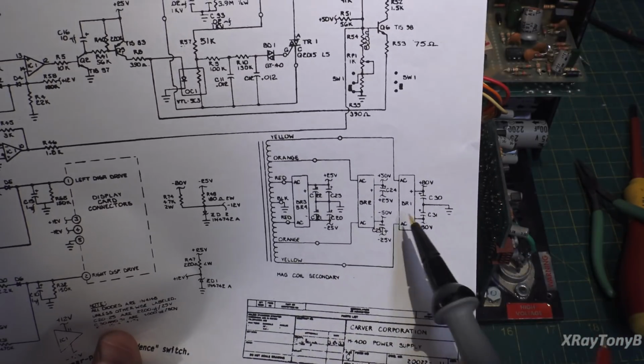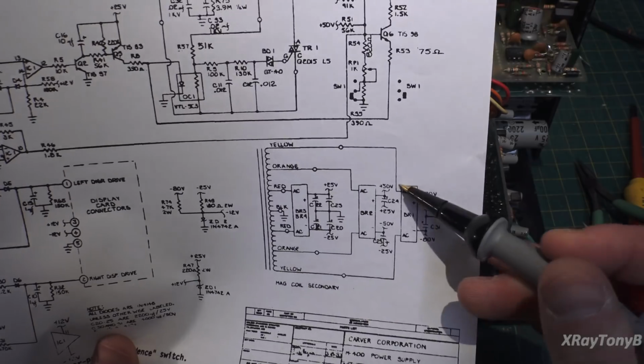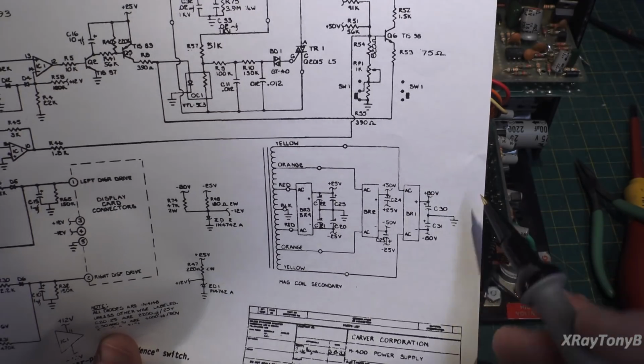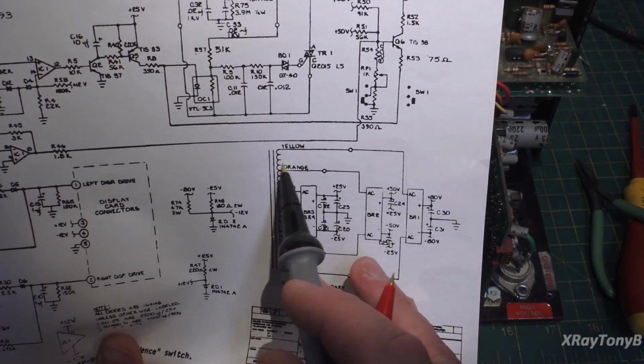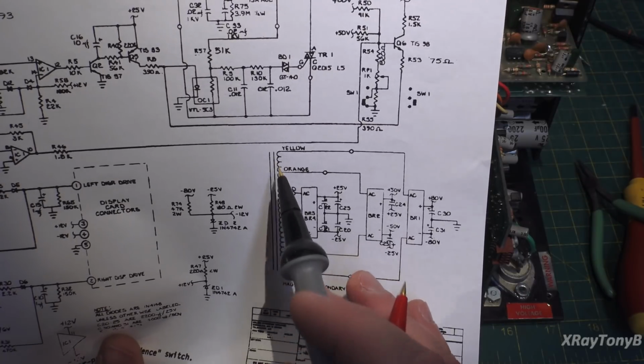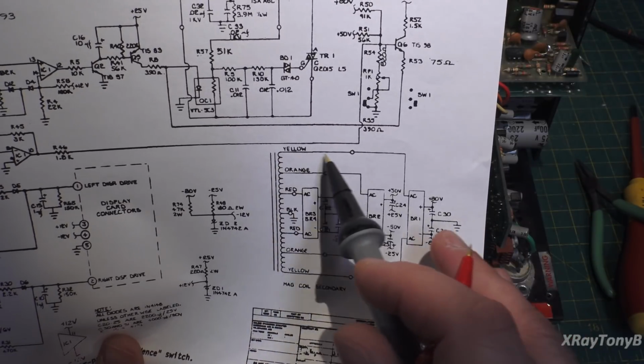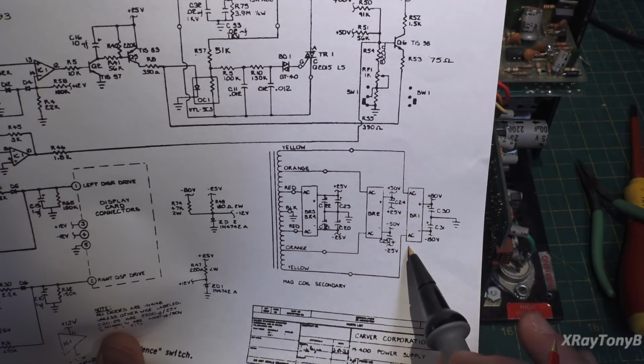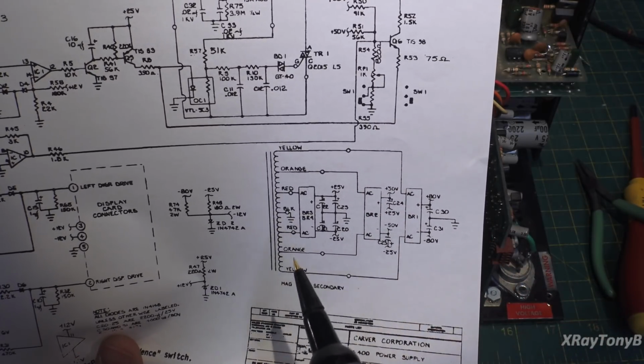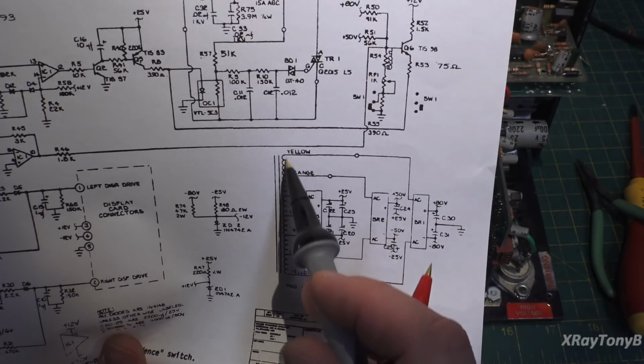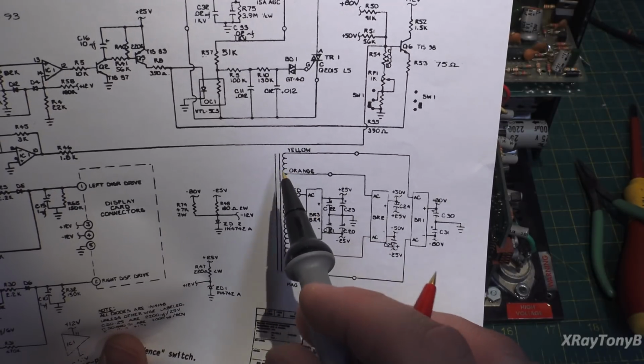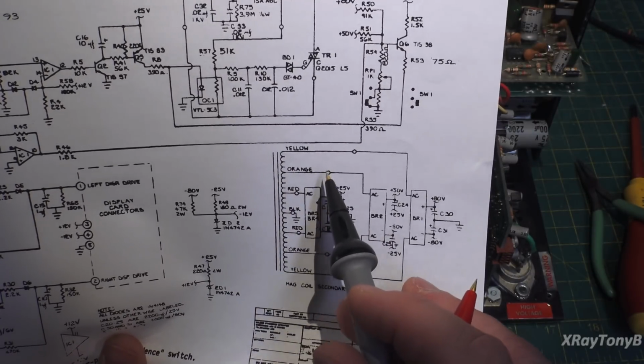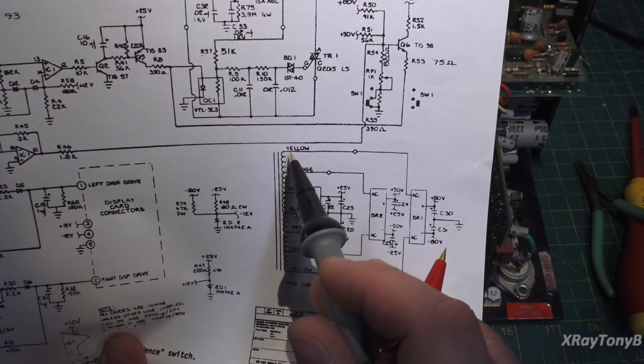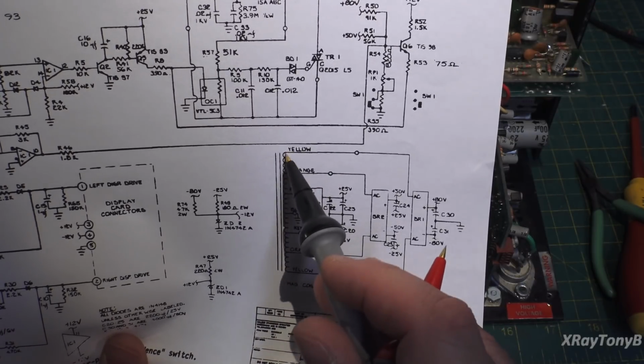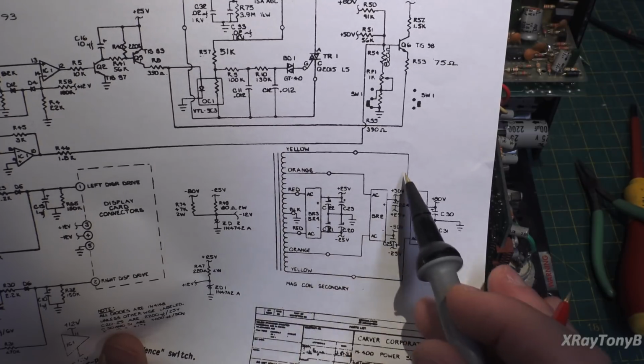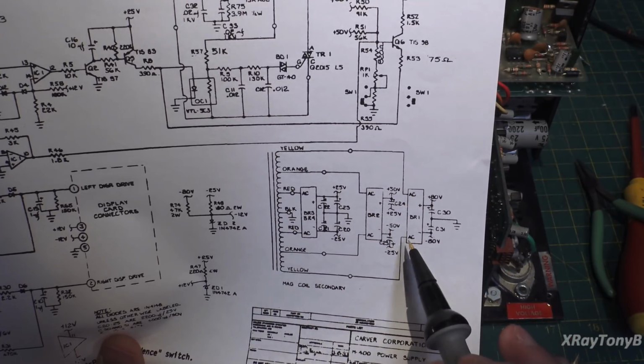Because of that, if one of these bridge rectifiers is shorted and the winding here is actually open, and I try to read continuity, I'll read continuity through the shorted bridge rectifier and mistakenly think the coil is good. So you really can't test this in circuit. You have to remove the wires from the terminals so you know you're reading through the windings and not through a possibly shorted component.